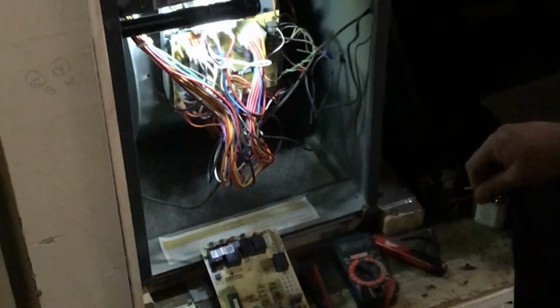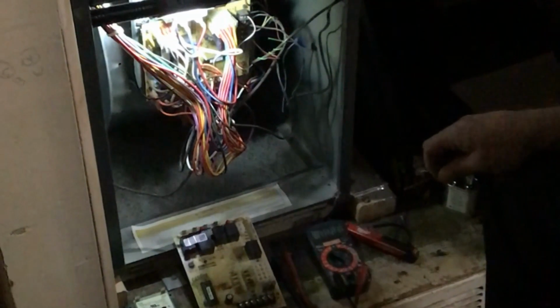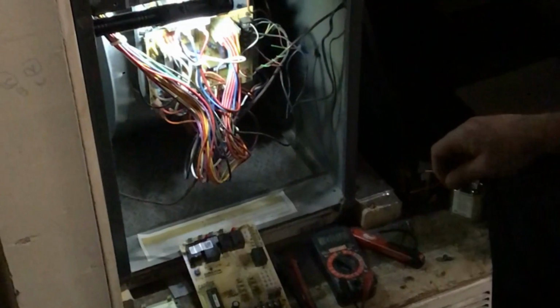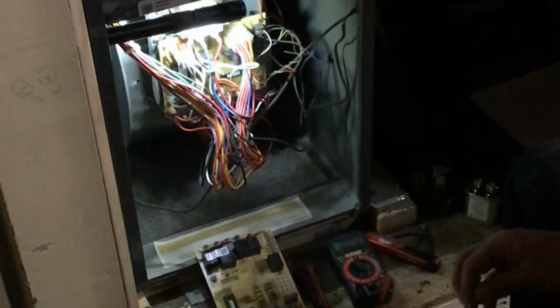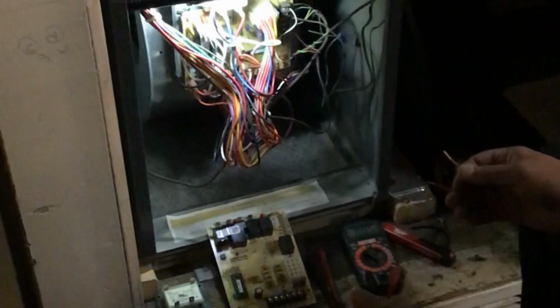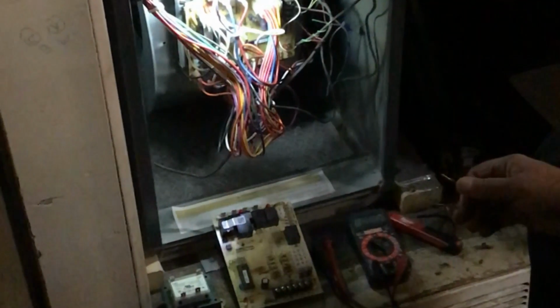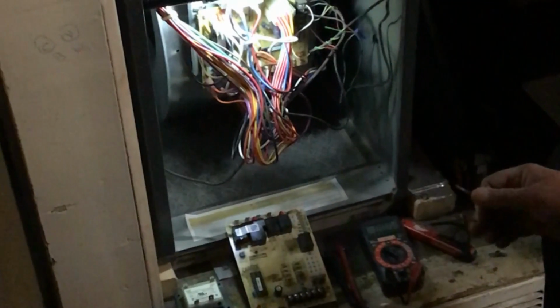Okay, so we spent the first segment of the video talking about 240 volt problems. We spent the last segment talking about 120 volt problems. And so now we're going to focus on the control system, or the 24, the low voltage. I don't mean to get out of sequence, but we just discussed fan operation and what sort of 120 volt problems would cause the fan not to run, or how you could determine if the fan was bad. There actually is a 24 volt problem which could cause your fan not to run.